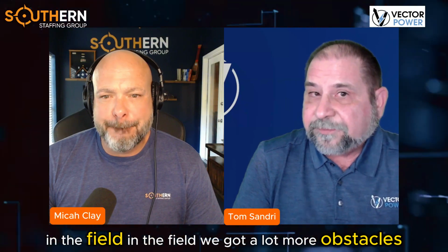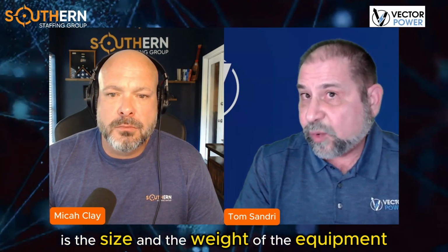Now you have the discipline that is adopting it and using it in the field. In the field, we've got a lot more obstacles. When we talk about field testing, you'll see references made in the literature to IEEE 400.3, which is the particular guide I want to focus on. In there, they talk about the different ways that we can supply test voltage. We can supply test voltage using 60 hertz, but one of the limitations you run across with 60 hertz testing in a field environment is the size and the weight of the equipment.